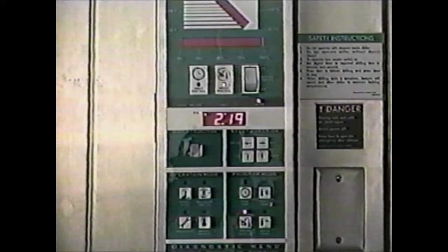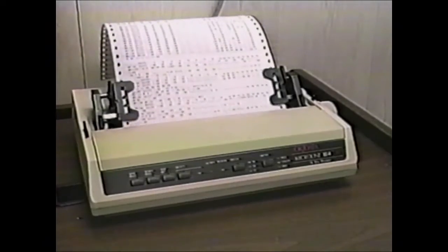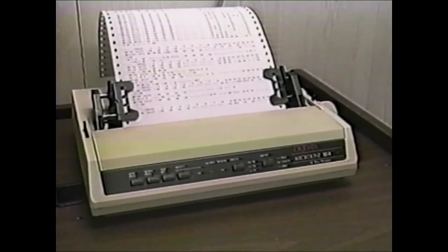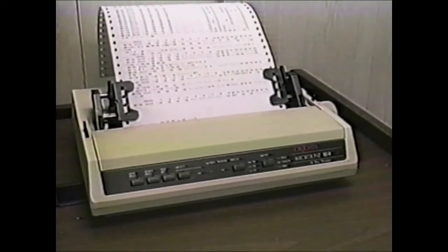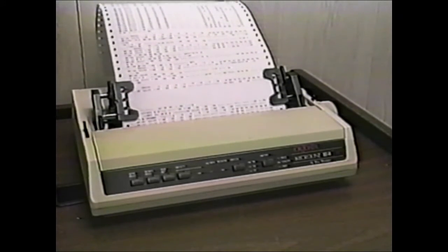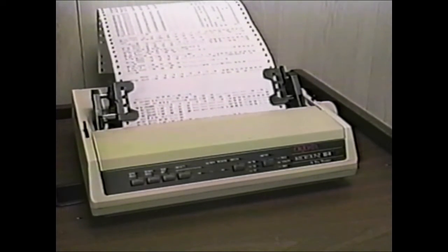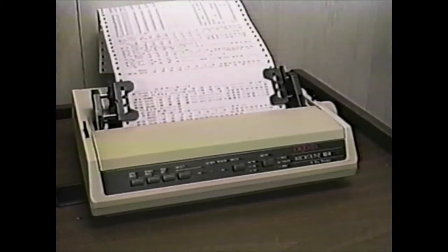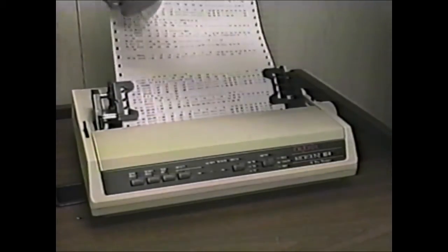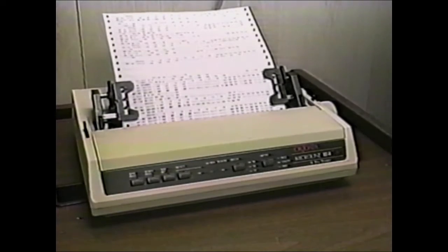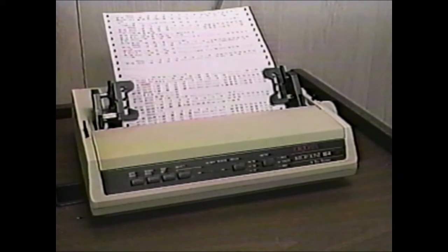Selecting on will permit the serial printer's ready to send signal to control the transmission of data and thereby prevent printer buffer overflow. Printing of the stored temperature data should be done directly to a serial printer through a 9-pin RS-232 serial cable. The printer must be compatible with either 1200, 2400, 4800, or 9600 baud rates. The following set points are adjustable within the ranges listed.